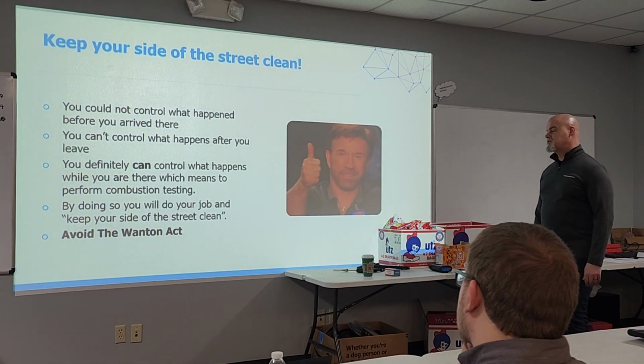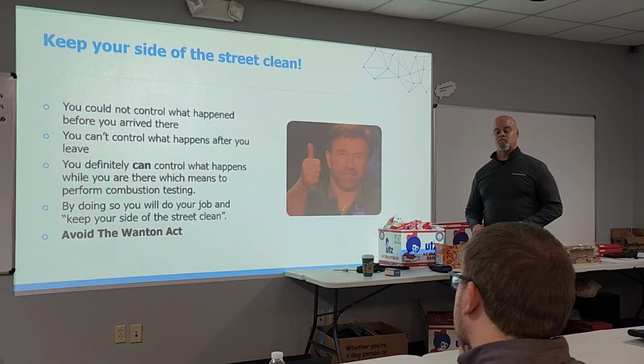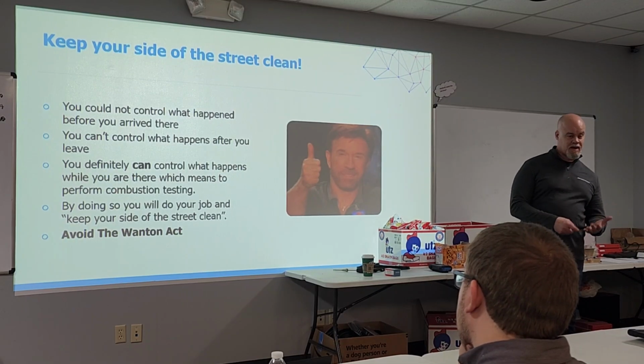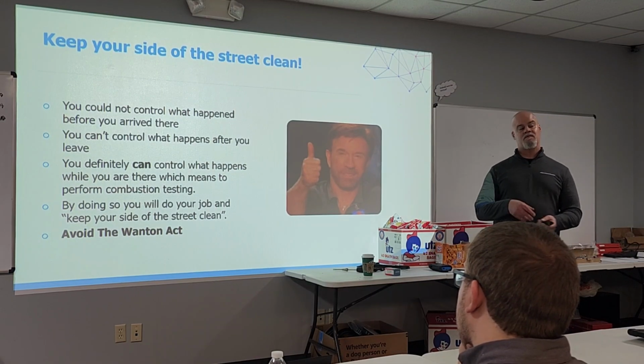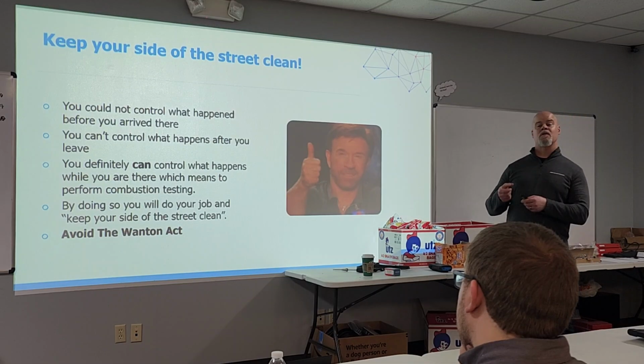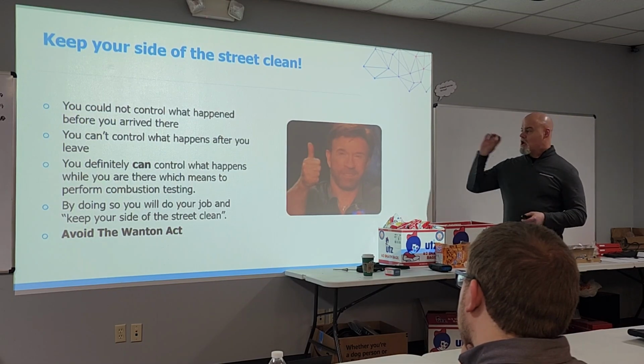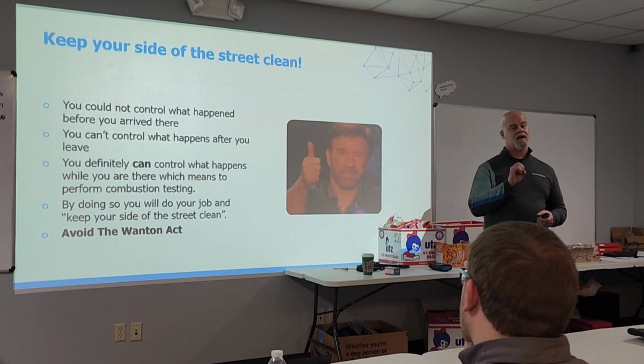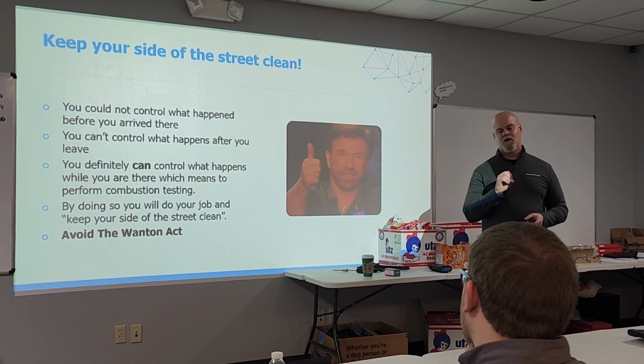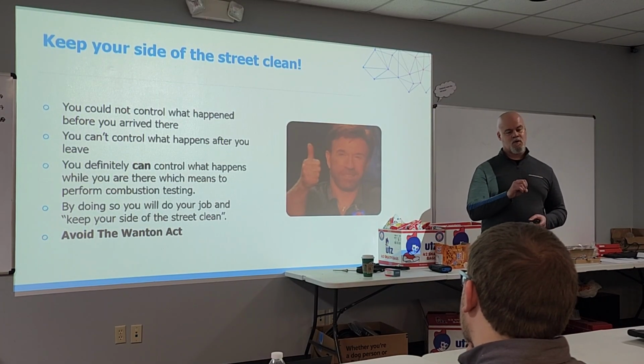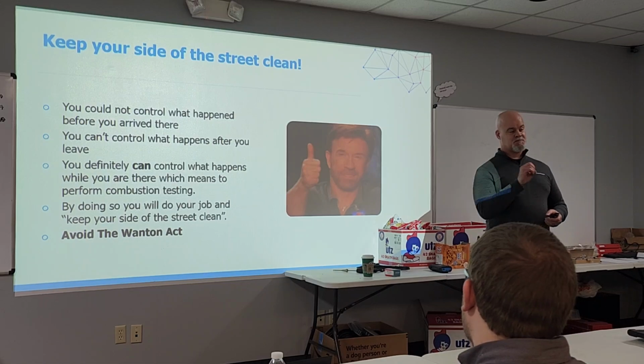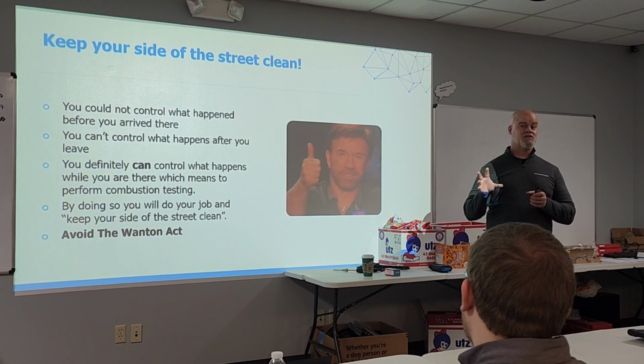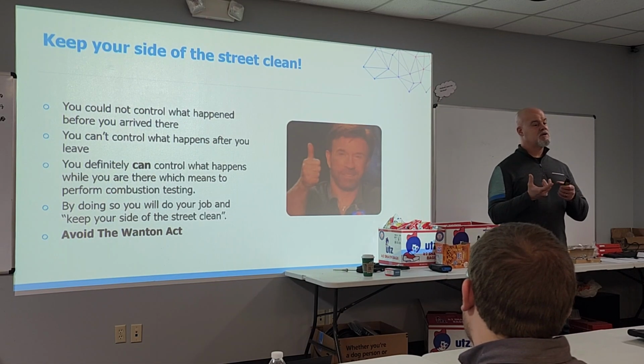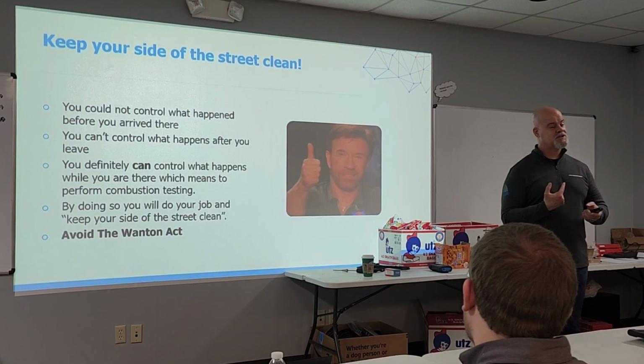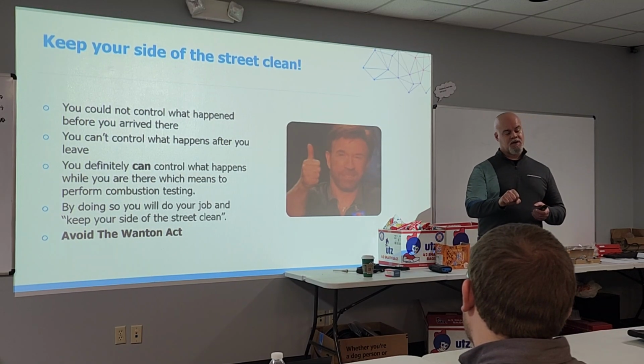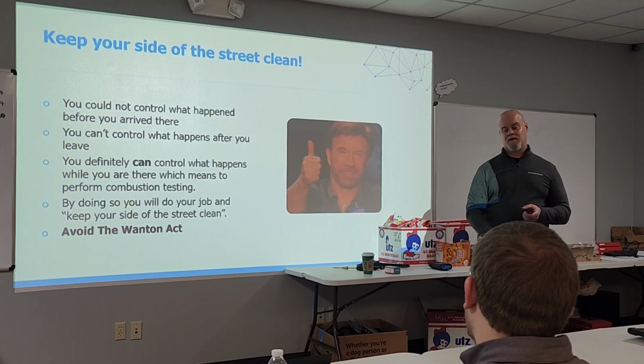In the words of the great Chuck Norris, keep your side of the street clean. What does that mean? You cannot control what happened before you got there, and you cannot control what happens after you leave, but you can control what happens while you're there, which means you do your testing. Your combustion test is a snapshot in time. It shows beyond the shadow of a doubt the state of health of that equipment and the way you left it, because people might come in after you and change things in that structure, altering your combustion readings and creating a volatile situation. However, you control the conditions that day when you were there, so you're not held suspect to that.